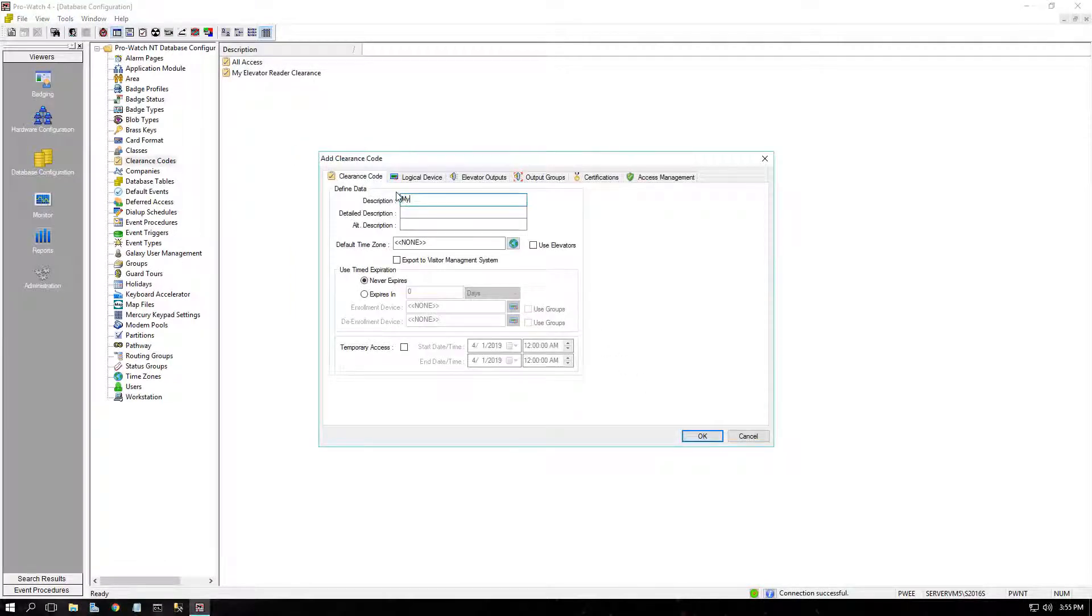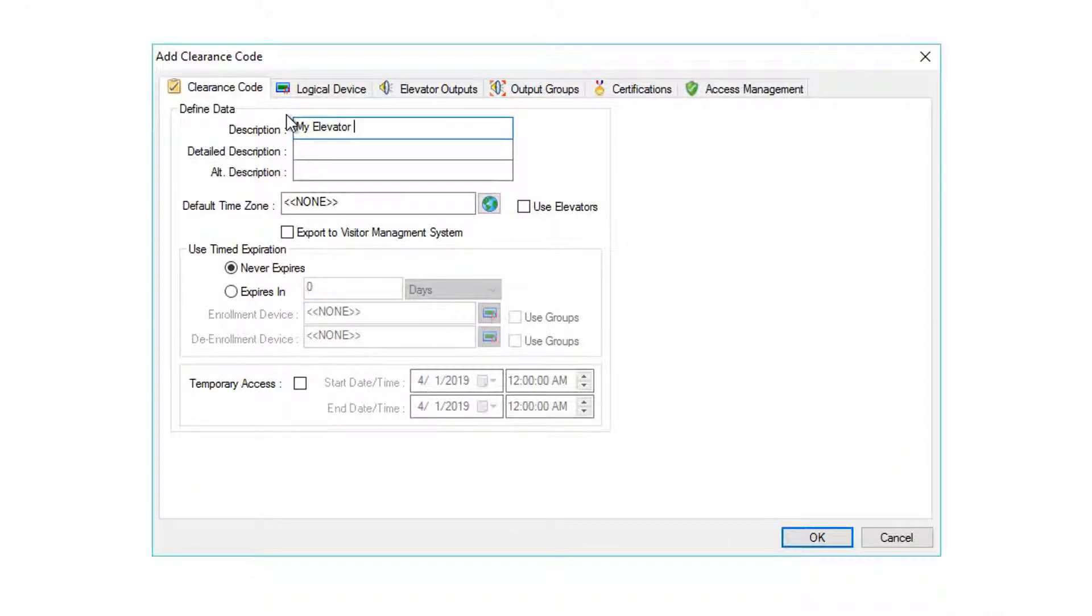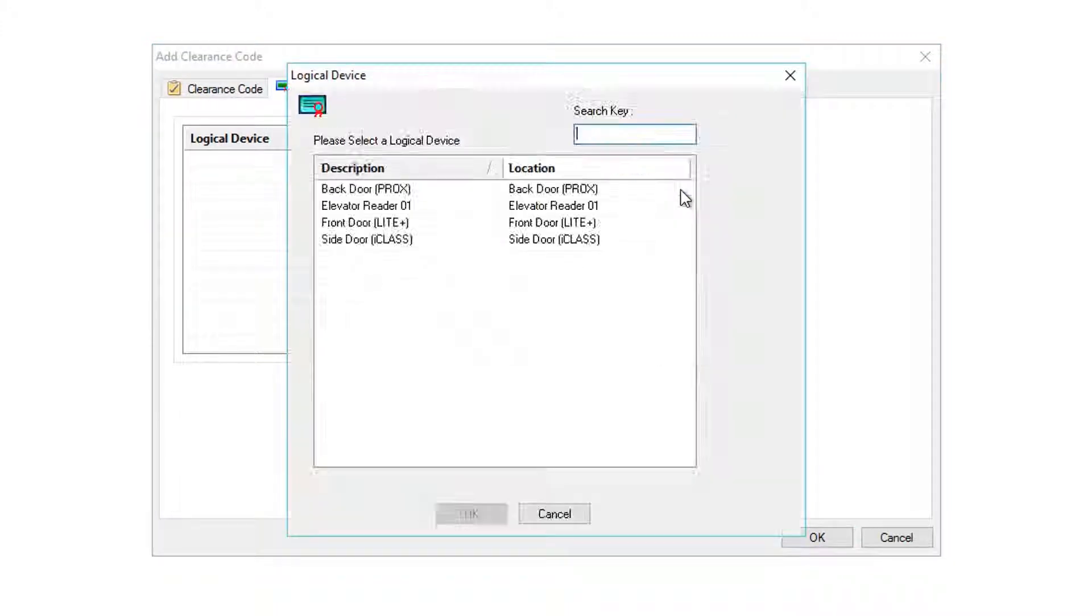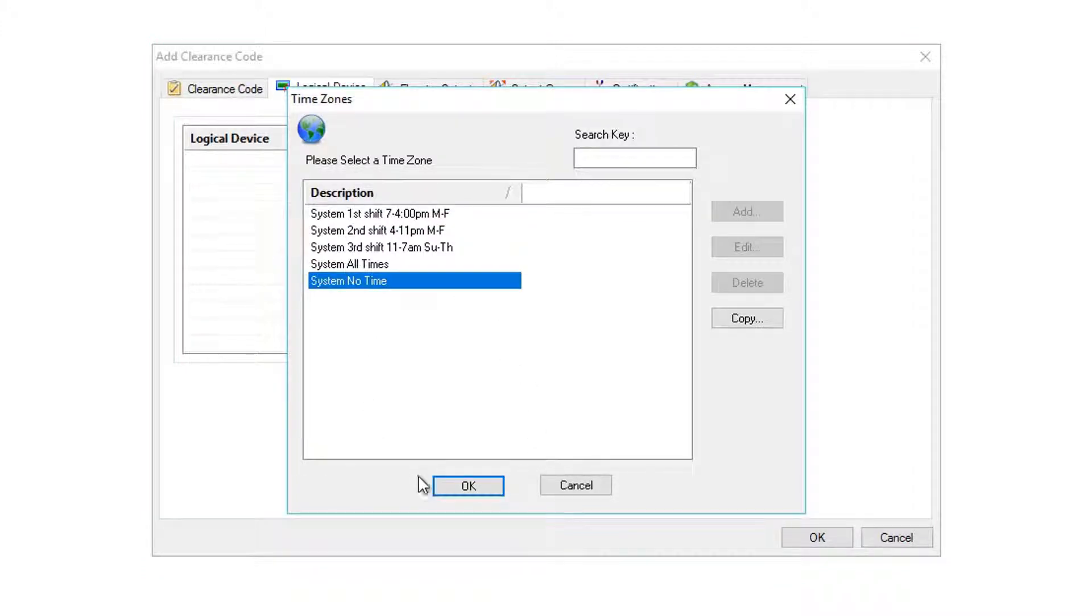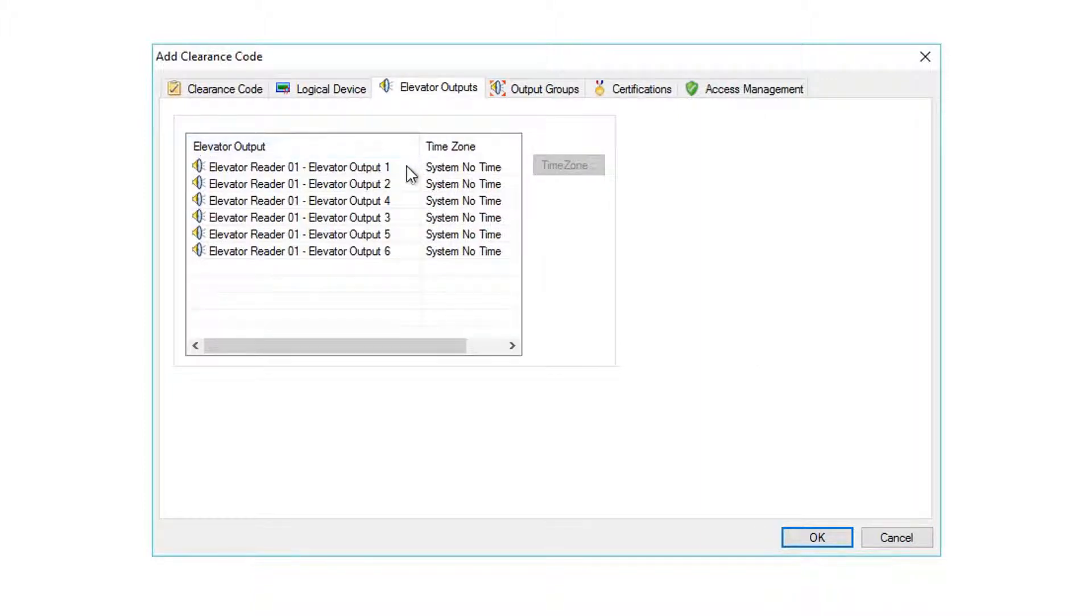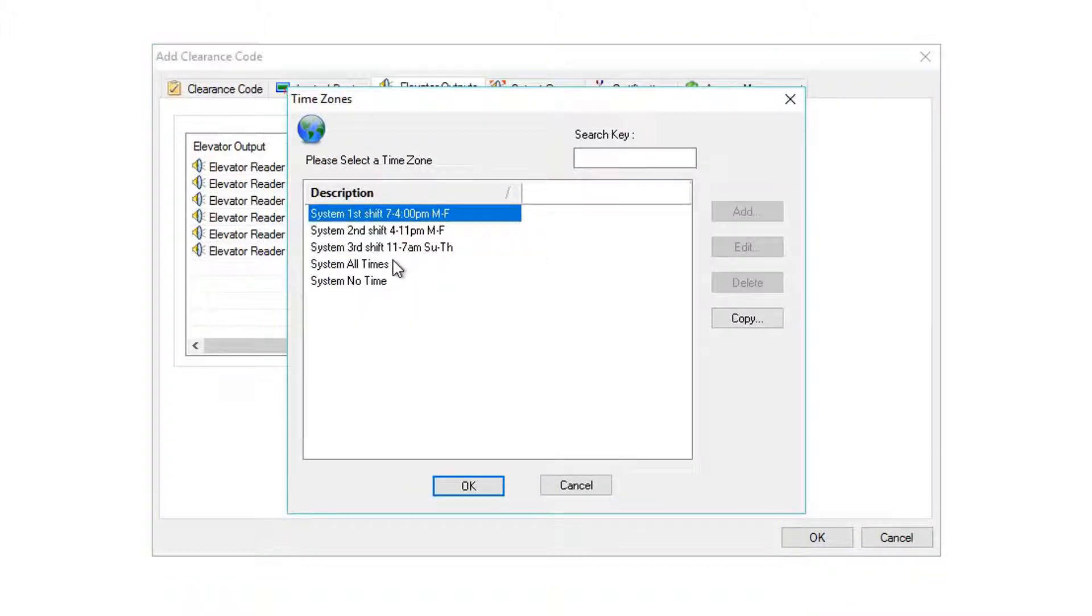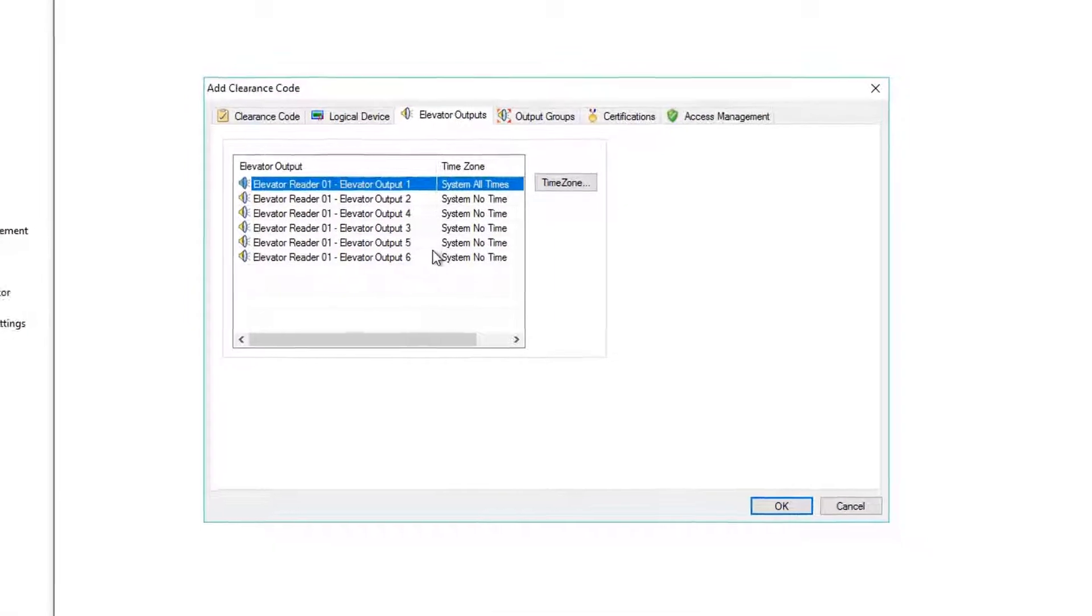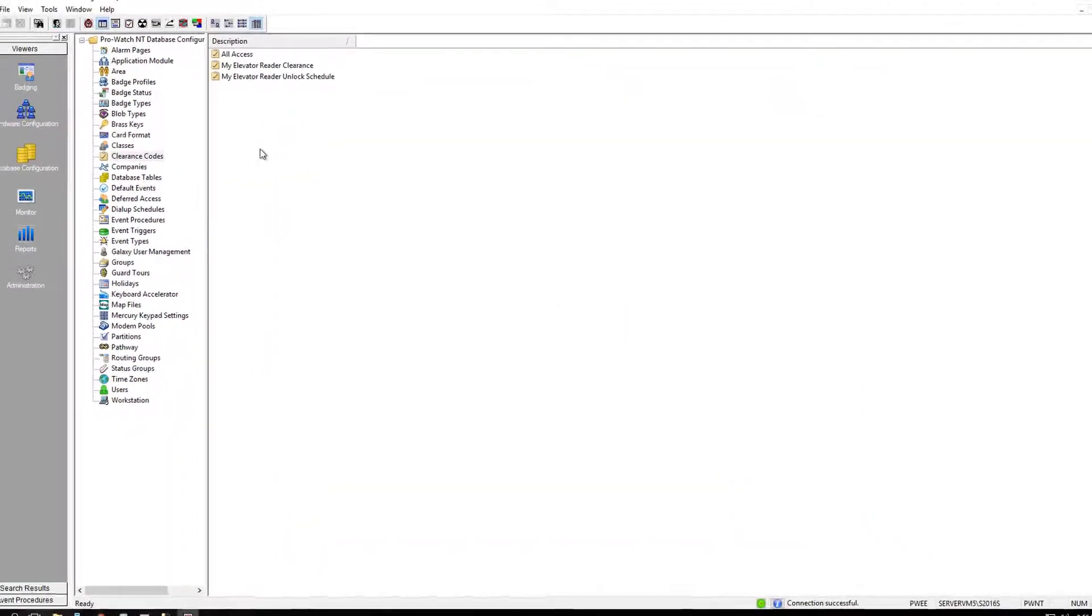Let's make another clearance code for an unlock schedule for an elevator. My Elevator Reader Unlock Schedule. Check Use Elevators. And on the Logical Device tab, click Add and let's find again our Elevator Reader. This time, we'll choose System No Time Time Zone, as most floors will not be automatically unlocked during the day. We'll find the Floor in Question, Floor 1, highlighted, and we'll say Time Zone, System All Times. Our Floor 1 is allowed to be unlocked 24-7. Other floors are never allowed to be unlocked.